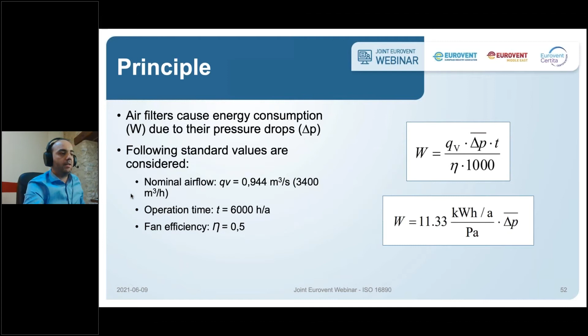So how should we rate the energy efficiency of an air filter? The testing method is as follows. You have to first carry out the ISO 16890-1 tests for a full-size air filter. Then you have to load the filter with ASHRAE dust according to the ISO standard 16890-3. It's the standard belonging to the same series as the -1.